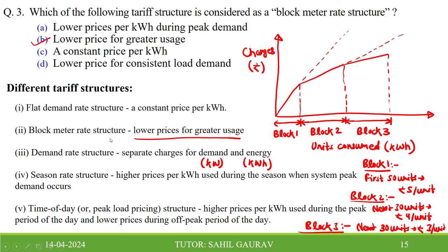While this block meter rate structure means lower prices for greater usage. And this figure represents this block meter rate structure. As you consume more energy, the prices will get reduced. And then demand rate structure, that is separate charges for demand and separate charges for power and energy, for kilowatt and kilowatt hour.